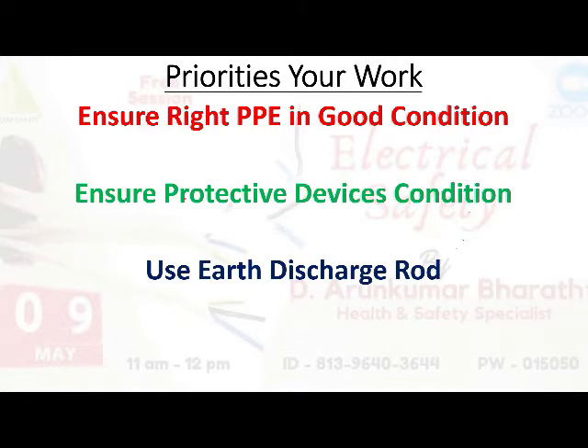Residual current can be present not only in capacitors but in any UG cable more than 2.5 square mm. Whatever the high tension voltage, the cable will usually have some residual energy, so we have to discharge it using an earth discharge rod.